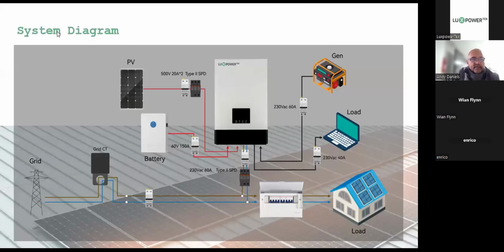System design. Okay, so here we have a typical schematic of what the design would look like. So starting on the left-hand side here, we've got the grid coming in. The schematic is slightly wrong because it has both the live and the neutral going through the grid CT. Only the live goes through there, okay? So the neutral will go through here. The SNA 6 is shipped standard with an external CT. And unlike the LXP range, it's not mandatory that you fit the external CT. But if you want to export grid and have the machine compliant with your municipal application, then you're going to have to fit the CT.